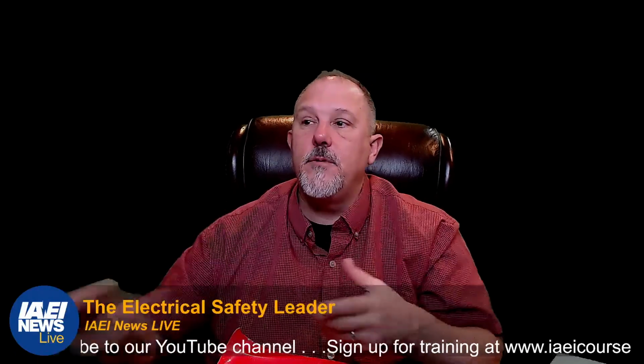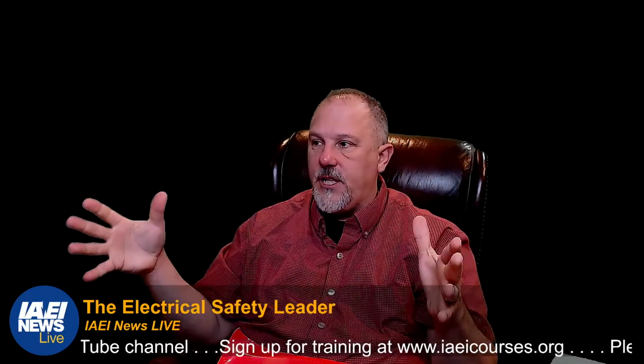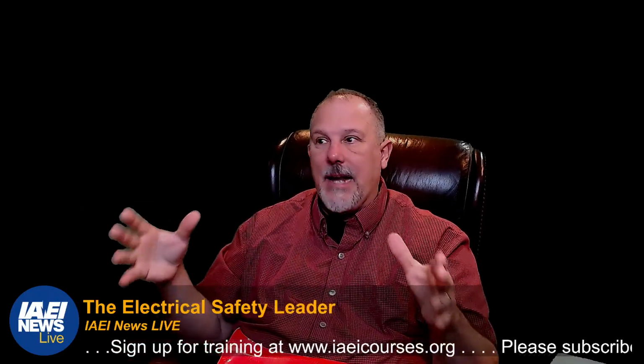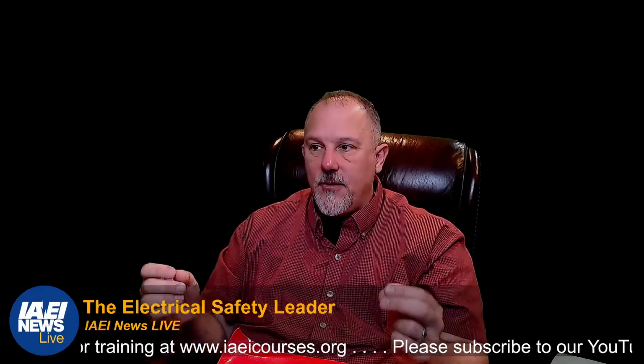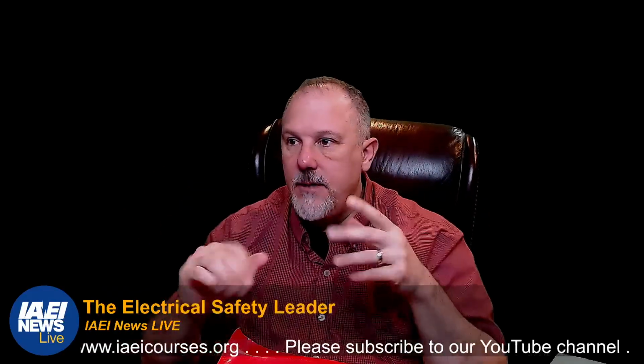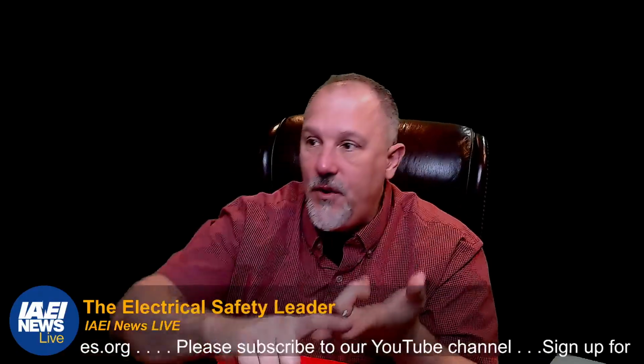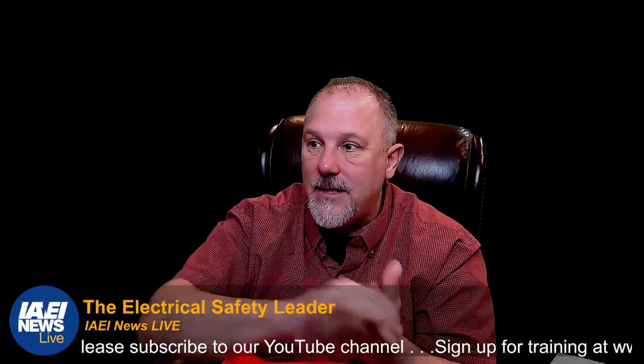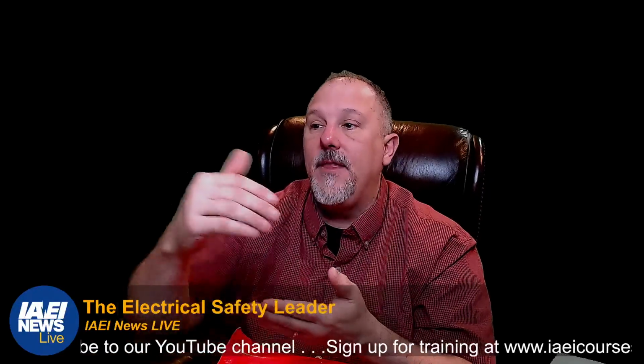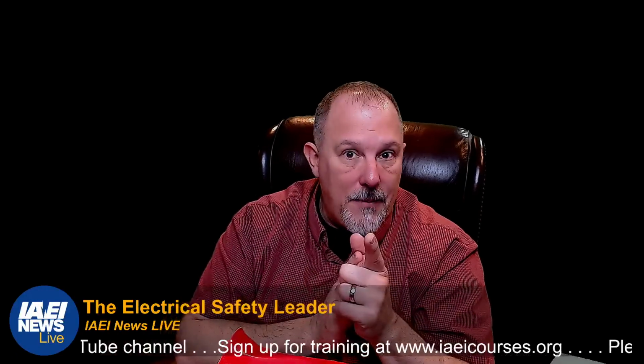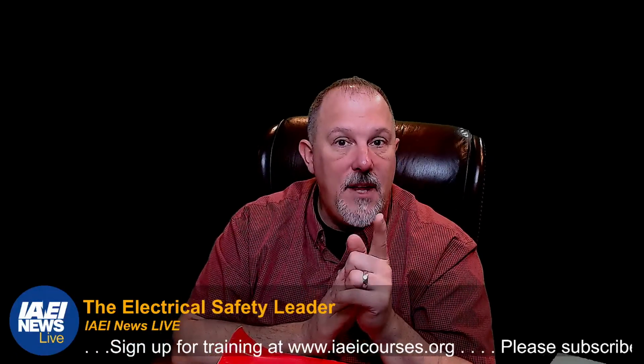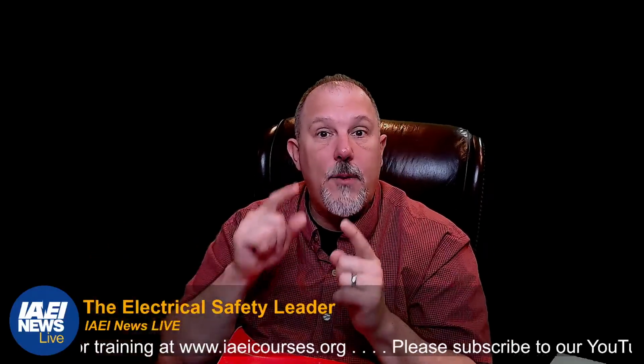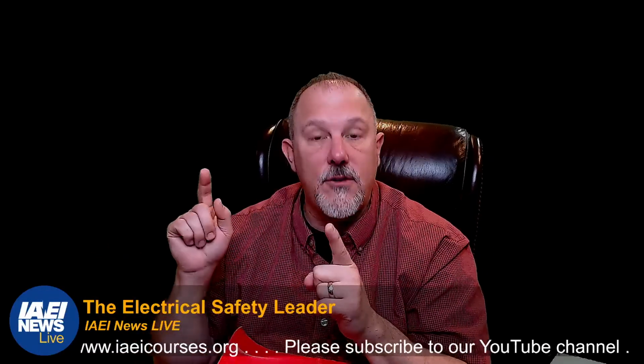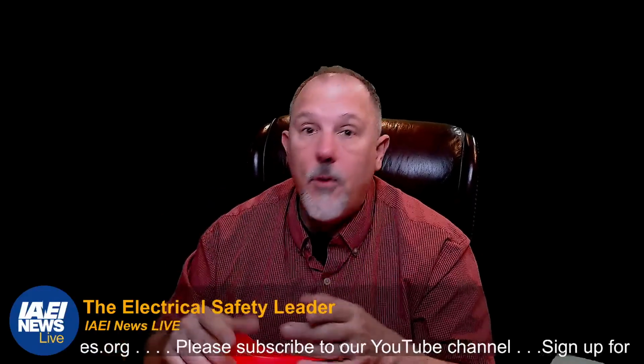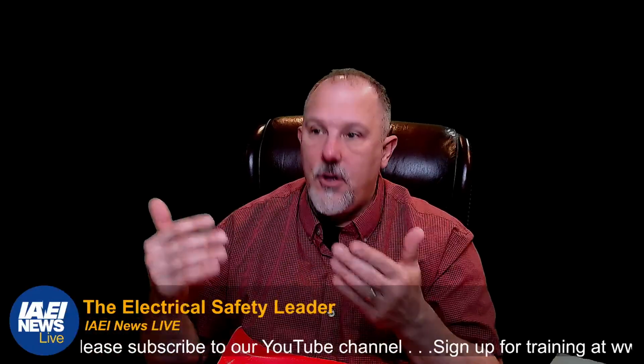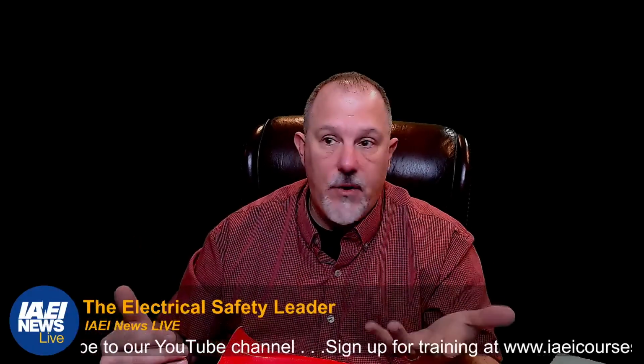What do we do for visual inspections? We do an external physical condition check. This includes condition and integrity of any applied labels. We inspect anchorage and grounding, how it's mounted. We look at the circuit breakers, fuses, and the overload elements to see that they're the right size and that they correspond to the drawings and the power system studies. Now, what does that mean? We picked that up because if you have a selective coordination study, you want to make sure that whatever breakers are supposed to be there based on the selective coordination study or the short circuit study and the equipment evaluation study, you have the right breakers and fuses.